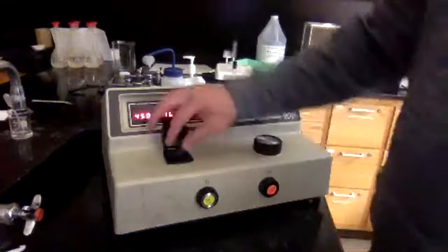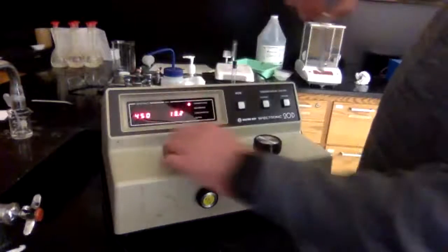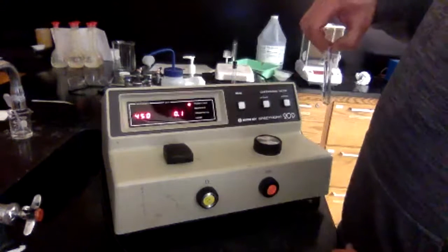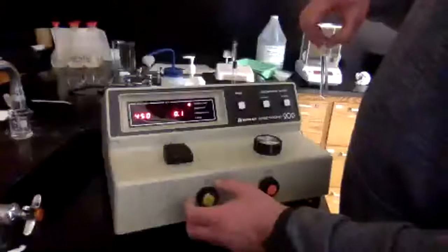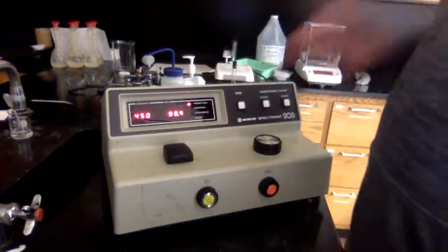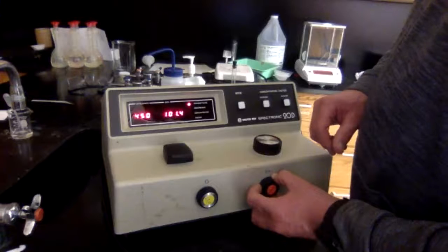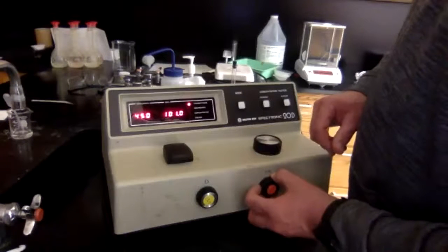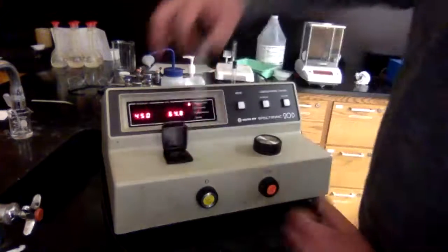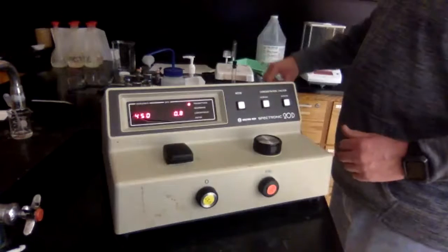All right, so then we are going to pull out the blank because now it's at 0, a little more, and 100, 0, and with the blank, 100. So the equipment is now set. Oh, you son of a gun. That's probably because it is warming up. As the bulb gets hotter, it's going to change things a little bit. That's why we run them for 15 minutes before. We don't have time to sit around here for 15 minutes.